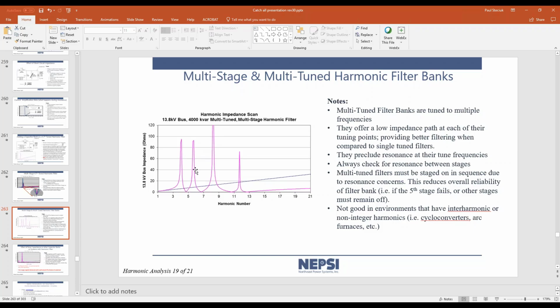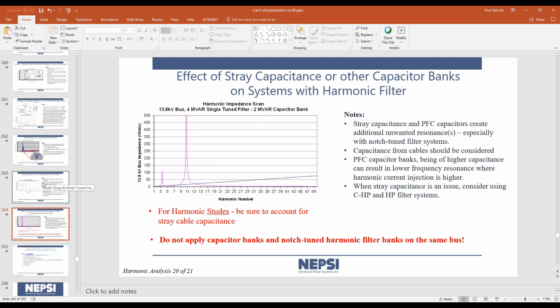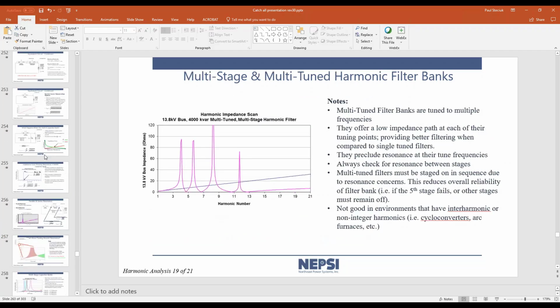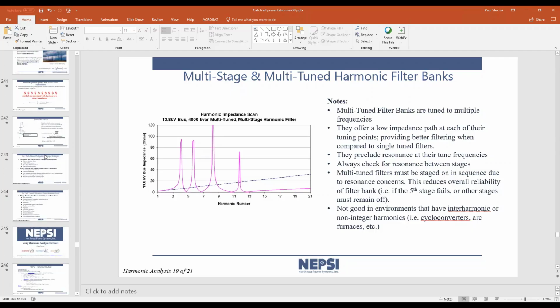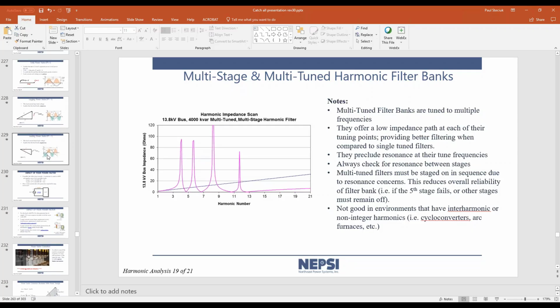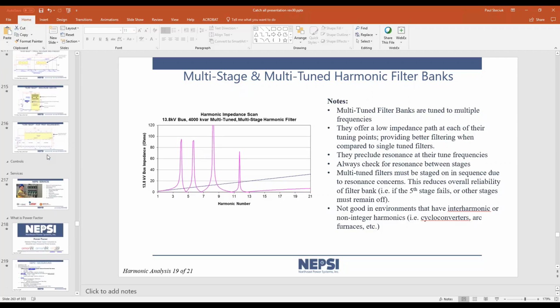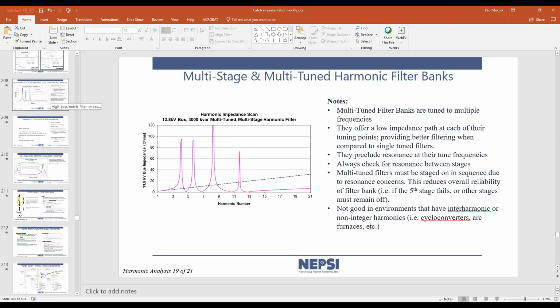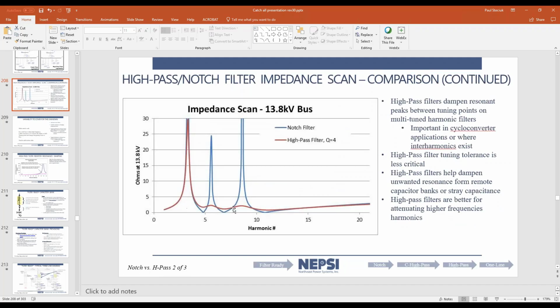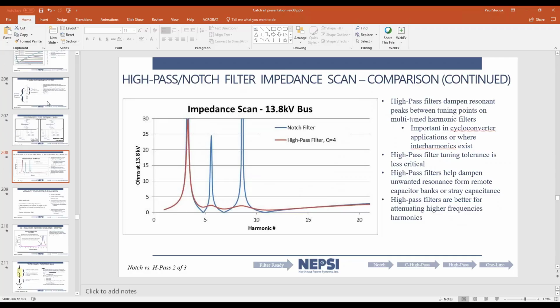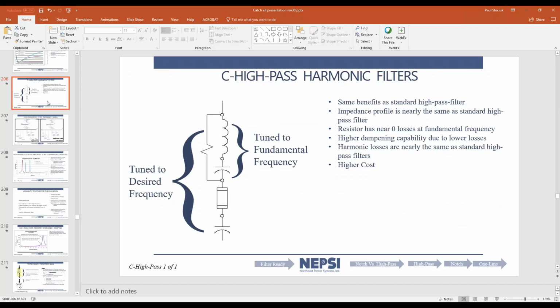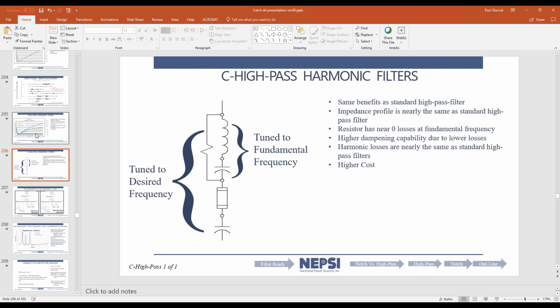So these are resonance concerns, and when you have harmonic producing devices that might be at these locations, they are of concern. It's a resonance concern, and the correction to such a system is to put in a C high pass or high pass harmonic filter branches, and that is how you eliminate that concern, is by the use of an appropriate filter. So it's a more expensive filter system, and it kind of comes back to where I was here with eliminating that through a C high pass or high pass type harmonic filter. So that's exactly what you're looking to do. So it'd be this type of filter, or this type of filter, or this type of filter.